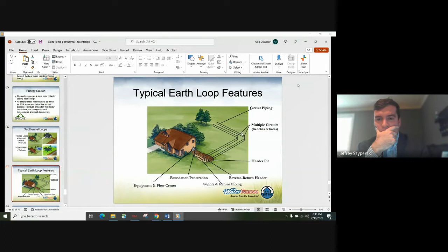Here's an example of one that's been installed in the field. You can see the pipes pinned up against the side here, and then this is all backfilled. Once the loop is filled back, there's typically some settling - obviously, if you disturb soil, you're gonna see that on a construction site. But once it's in there, the life expectancy of that loop field is over 100 years, unless for some reason it is damaged. We put tracer wire in ours so that we can find them in case you need it down the road.